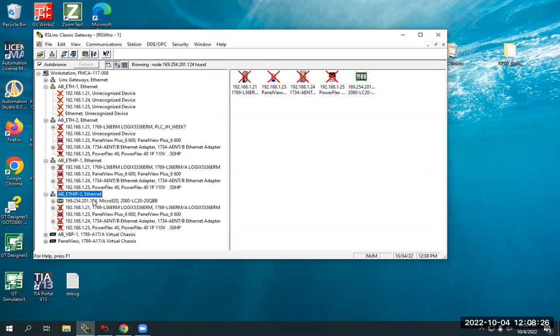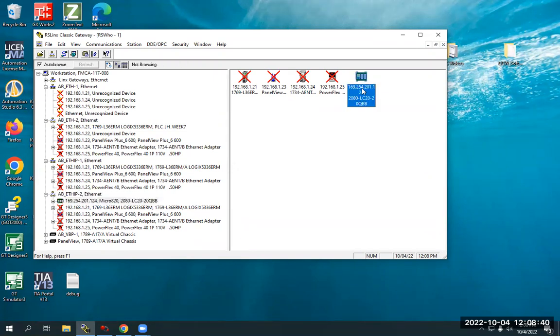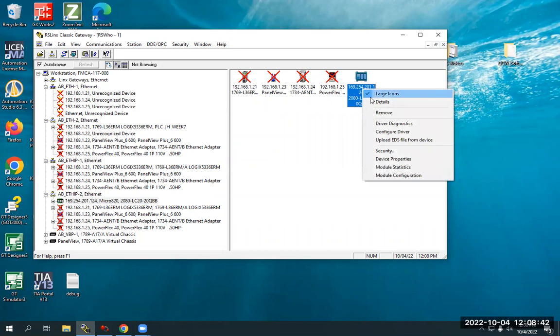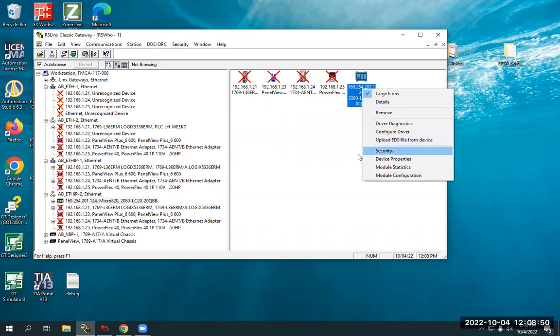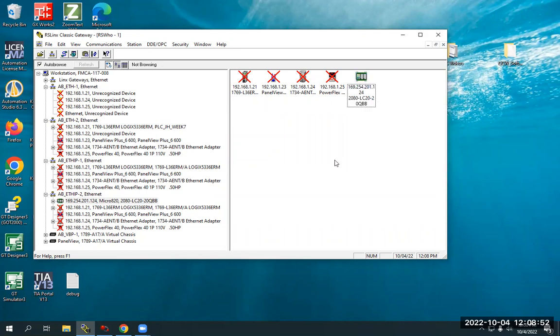And what that means is originally when I found this, it said 169.254.201.124, Micro 820. And then it had a question mark here instead of the device. All you have to do is right click on it, the device itself. And when you do, you'll see this Upload EDS File. So if you have a yellow question mark, just click the Upload EDS Files from Device. And what that'll do is you'll basically hit next through it and it'll pull the image file and the EDS file from the controller and load it into RSLinx. And now you have an identified connected device here with the proper name and the proper image.